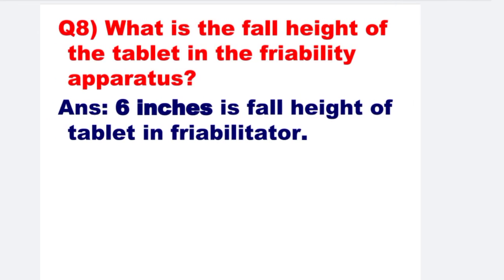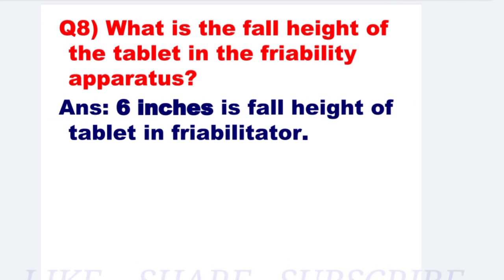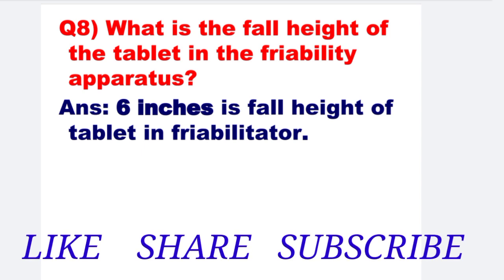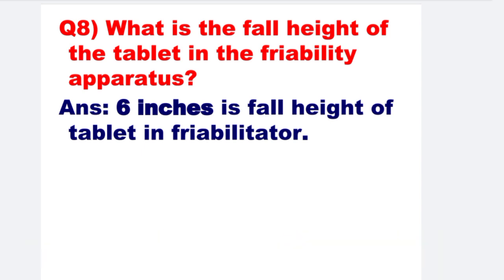Next: What is the fall height of the tablet in the friability apparatus? The answer is 6 inches is the fall height of the tablet in friability.